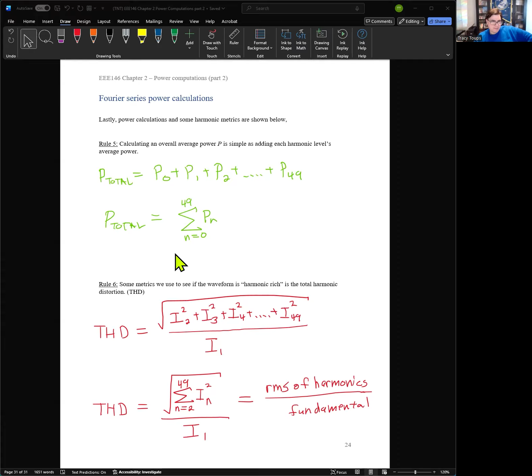Okay. So the last optional part we could do is, once we have the total power and the total RMS current, those are real life quantities, we could figure out a ratio called total harmonic distortion. And some places use this as a metric to see how harmonic rich our environment is. So let's say we have a voltage coming out of a wall socket, right? The higher the total harmonic distortion, the dirtier the source is. The more harmonic content, the more noise, the more damage you could do. So a high THD is bad. You don't want this. Lower THD means you have a cleaner waveform, it's smoother, and that's what we want.